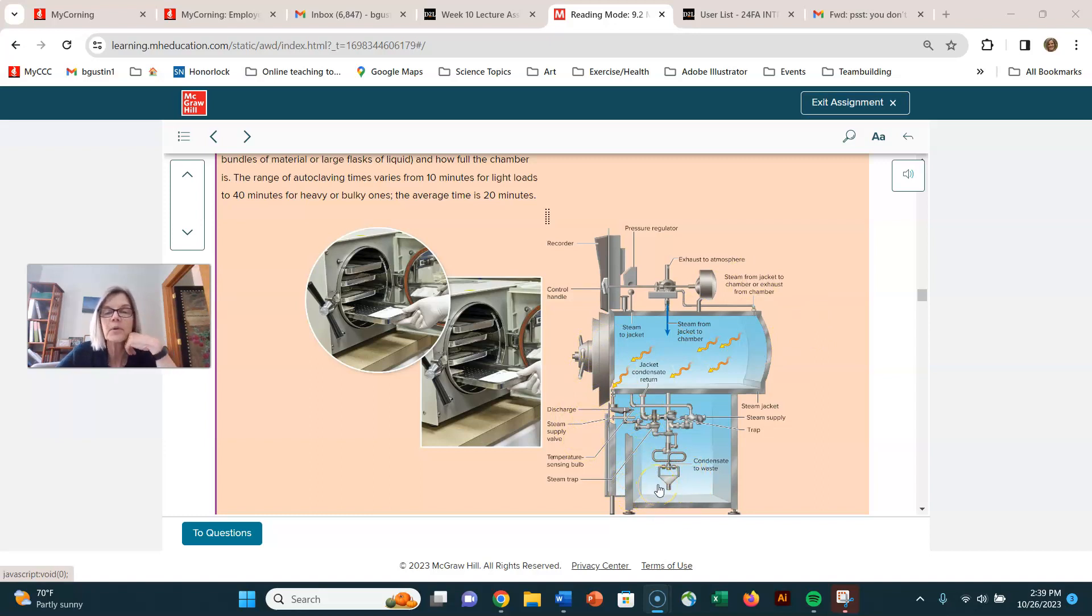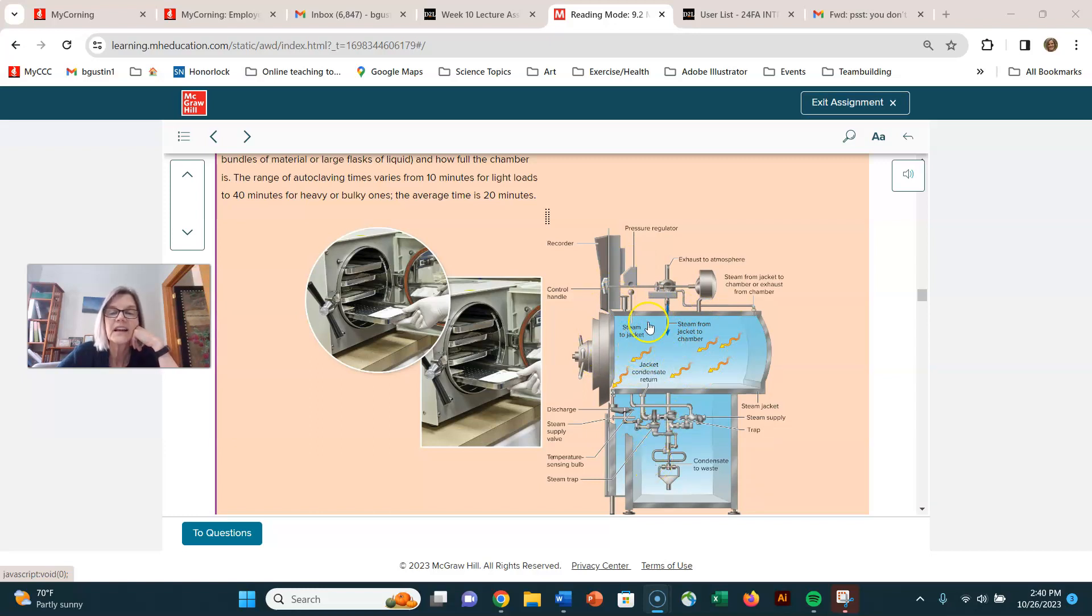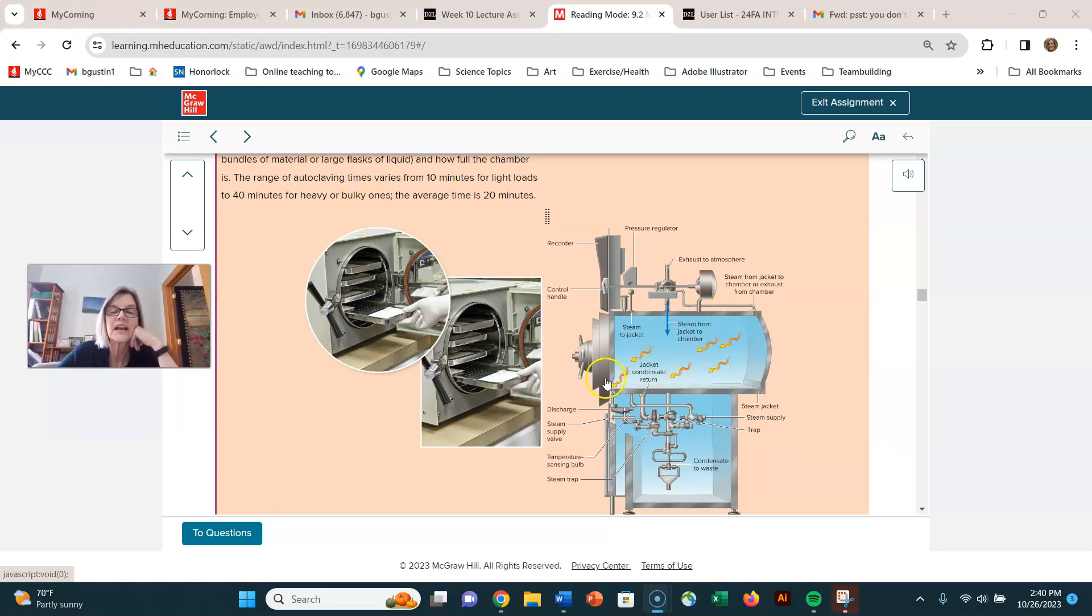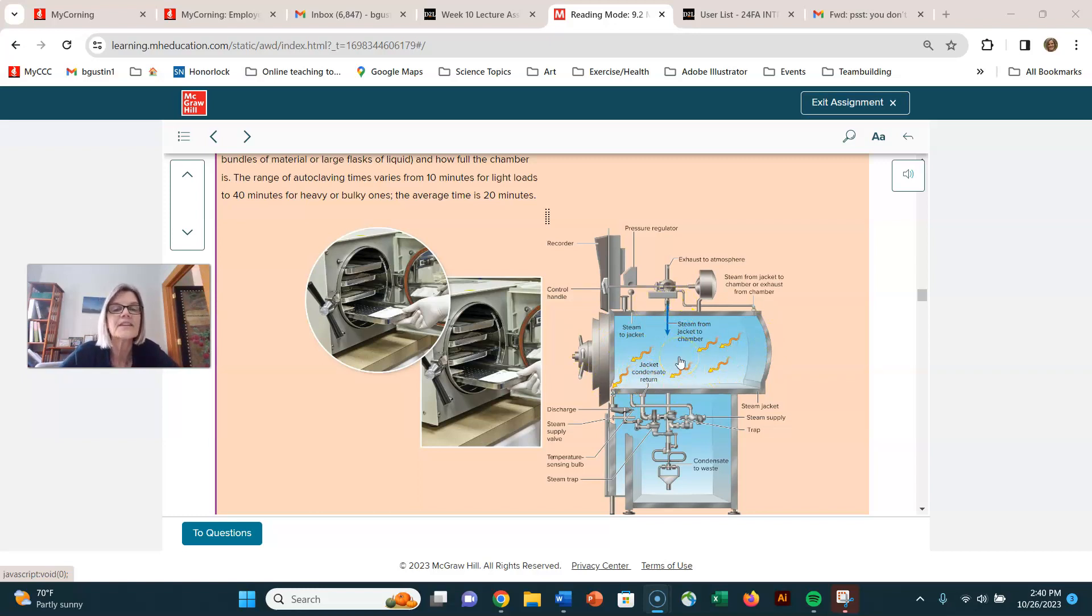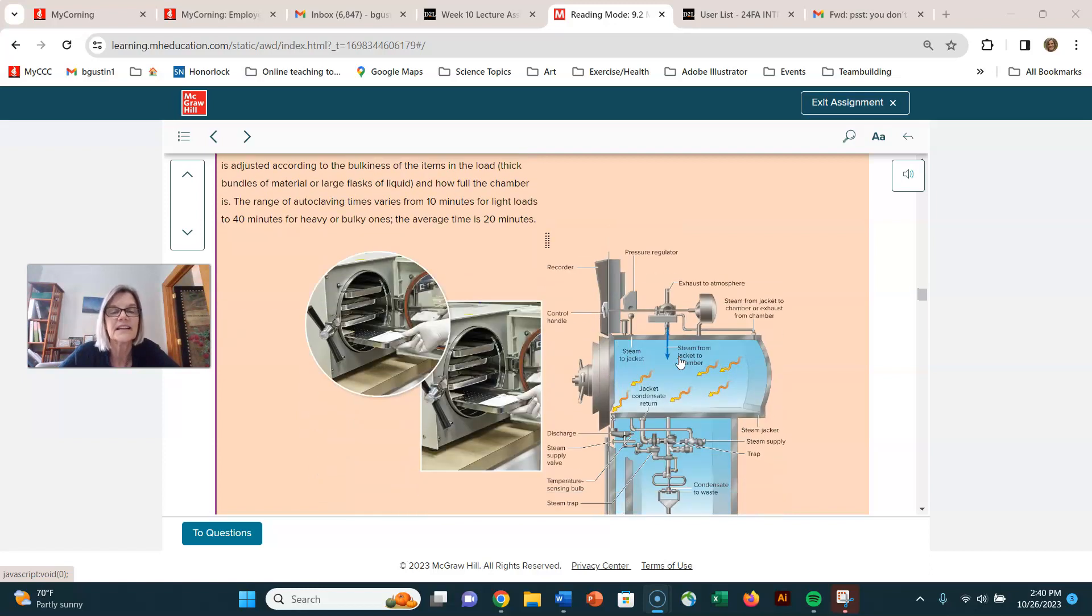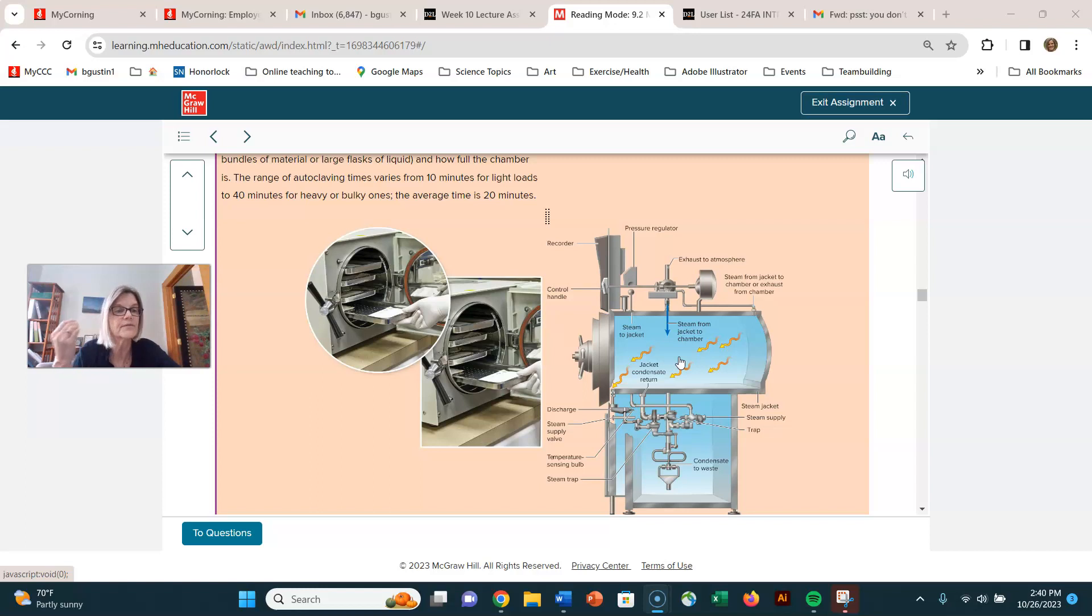It's kind of built into a wall and it has a boiler down at the bottom. That boiler is going to create some steam. You're going to be able to put your objects in here, close the door, and let the steam come into here. Because this is made of this really heavy steel, you can actually get the pressure up higher than atmospheric pressure in this autoclave. The idea is that if you can get the pressure up above atmospheric pressure, you can get the temperature above boiling.